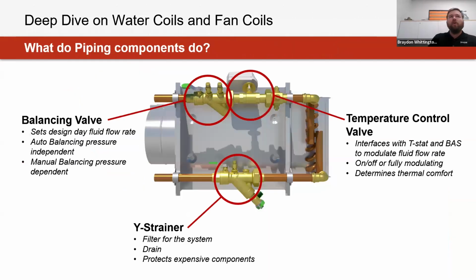Beneficial both from a quality control perspective, and for cutting down on the amount of time installing on site, but also for sorting out the logistics for some of these different components. So commonly what we would see paired with this equipment is temperature control valves. Essentially, you can even just visualize this as the damper of the system, modulating the flow going through that coil. A balancing valve is what sets that design day or maximum flow set point that we might want for that specific component.